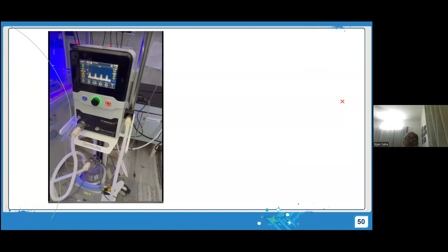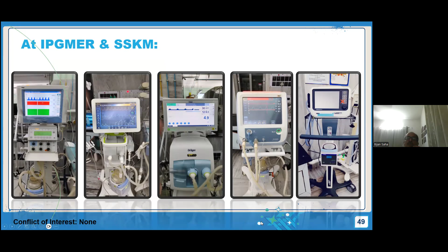Next, can you go to the previous slide? Previous slide, previous. So this is Babylog 8000 plus. In Babylog 8000 plus, you go to the IMV mode, and in that IMV mode you can provide NIPV. The only thing is that when you are using NIPV without a tube, using a mask, there will be pressure loss. In that case, if you use Babylog 8000 plus, you can keep the flow at a higher level, like 8 liters or 10 liters. So what we will find on the screen is how much pressure is delivered and how much pressure you have set. If the ventilator is delivering the same pressure that you have set, that means your flow is adequate.